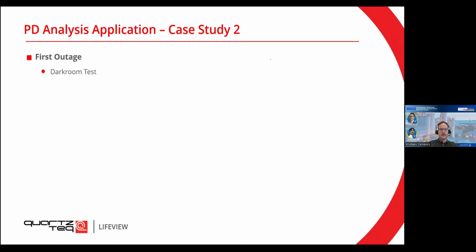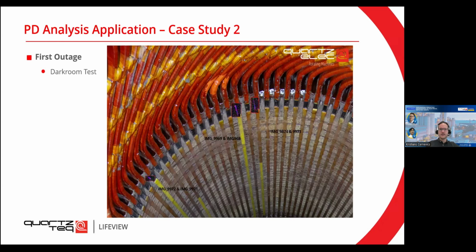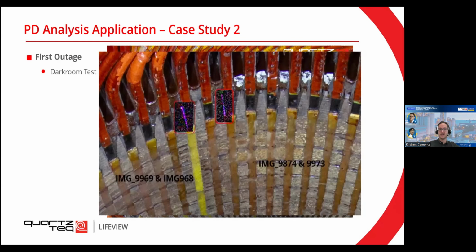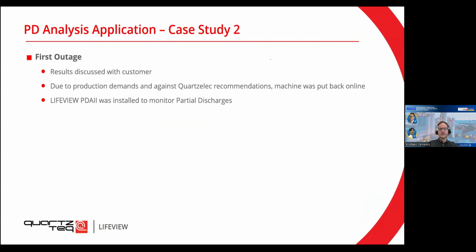They also did a darkroom test. So here, maybe there's a zoom in. Yes, there's a zoom in, so they saw these discharges happening in real time, and they saw the extensive damage already done by the partial discharges. Here, results were discussed with the customer, and it was suggested that the machine needs an overhaul. However, against the recommendations, because of the production demands, it was put back online. And at least the PDA2 was installed to keep monitoring the health.